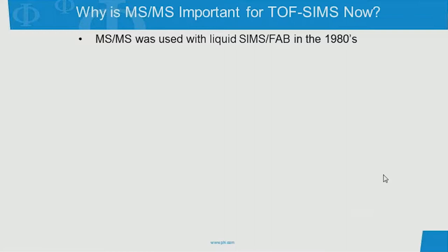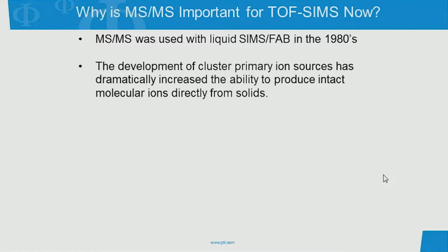Those of you that have been in the industry as long as I have might remember MS-MS was used in liquid SIMS, or FAB, back in the 1980s. But now we're finally introducing it to TOF-SIMS, and the main reason why is it's coming after the development of cluster primary ion sources. The introduction of these cluster primary ion beams to TOF-SIMS has dramatically increased the ability to produce large, intact molecular ions directly from solids.